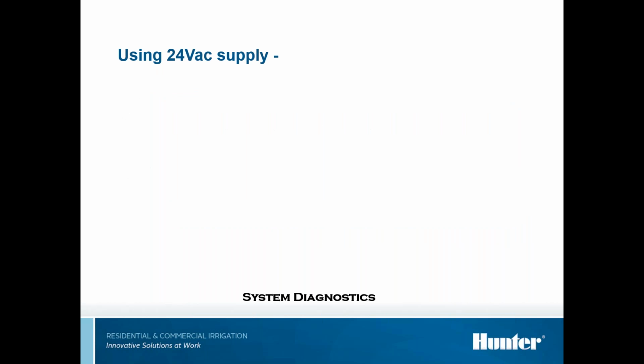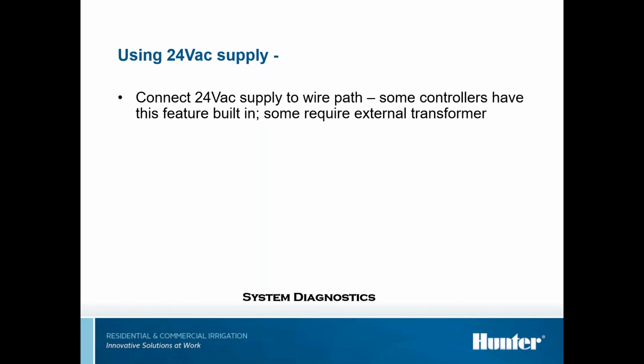Okay, so using the 24 volt supply, connect the 24 volt supply to the wire path. Some controllers, our ACC1, do not have the feature, so you would have to supply an external transformer. I've actually got on my truck a transformer out of an ACC controller, and that's what I use. But on the ACC2, that feature is built in, and I will be showing you in a minute where to find it. So you wouldn't even have to disconnect it to be able to put it in that 24 volt mode. Disconnect the controller wires first. On the ACC2, you would not have to because of the feature I just mentioned.